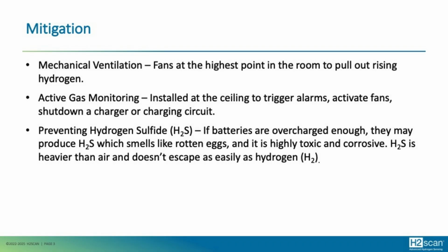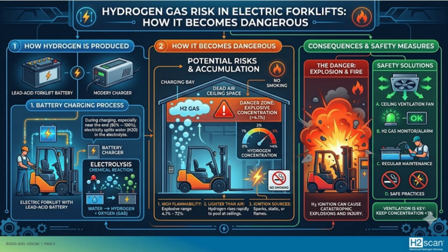And the H2S is the symbol for hydrogen sulfide, so I'll refer to that in this presentation. It smells like rotten eggs when you walk into a room. It's highly toxic and corrosive, so it will give you a scratchy throat if you breathe it in, and it can eventually make you very sick. And so we want to avoid this scenario as well. So monitoring for hydrogen also helps us avoid, or identify rather, that you have a serious overcharge situation that could turn into H2S. So how does hydrogen gas become dangerous?